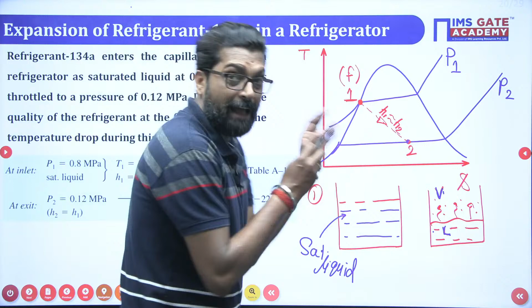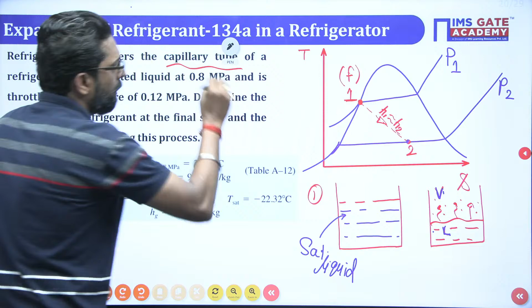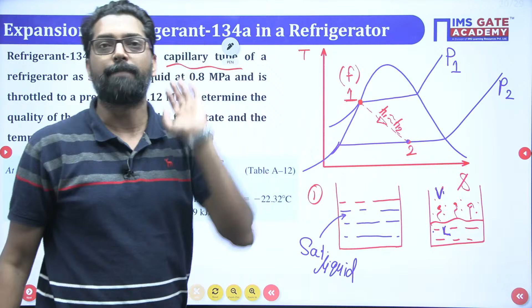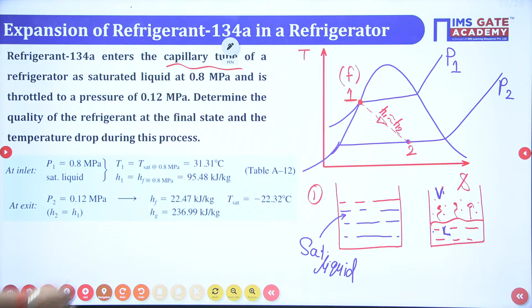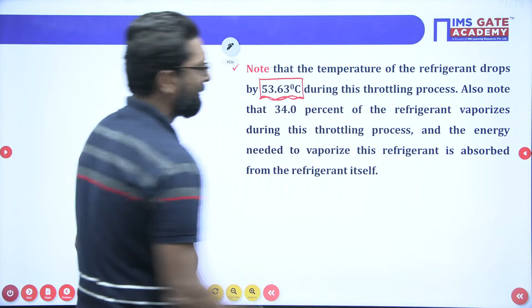Automatically the liquid refrigerant reduces its temperature. Clear? That's why in the capillary tube, when the refrigerant is passed, the exit condition has a very low temperature. If you solve this problem according to this data, the consequence is that the temperature of the refrigerant will drop by approximately 53 degrees centigrade.